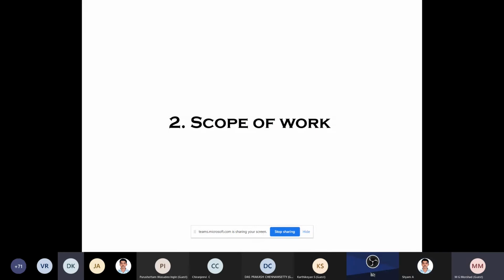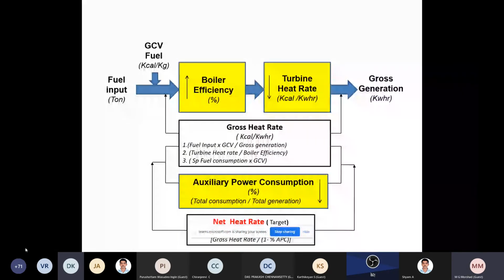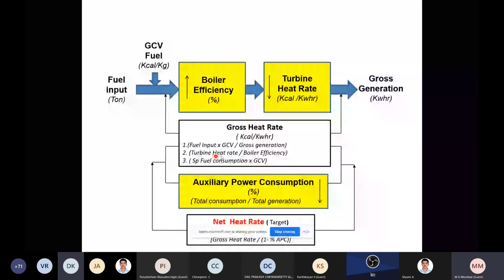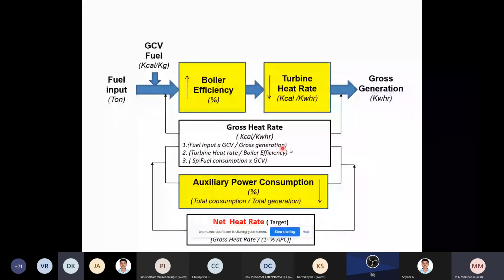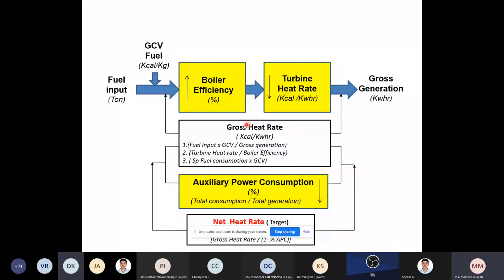Okay. Now the scope of work. I told you that writing the scope of work is a very big task, and it will run to pages together, which I will not be able to explain. So I have tried to present all these things in pictorial views so that everyone can understand easily. This is the basic flow diagram of any thermal power plant. Fuel input will be there, boiler efficiency, turbine heat rate, and gross generation. The first term coming is the gross heat rate. Gross heat rate is fuel input times GCV, gross calorific value, divided by gross generation. We can calculate it by three methods: turbine heat rate divided by boiler efficiency, and specific fuel consumption. Those three parameters will give the gross heat rate.